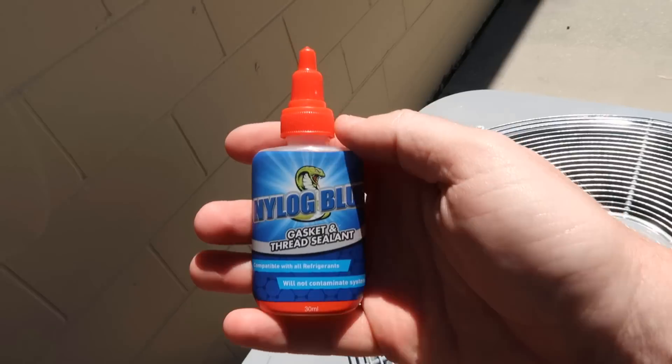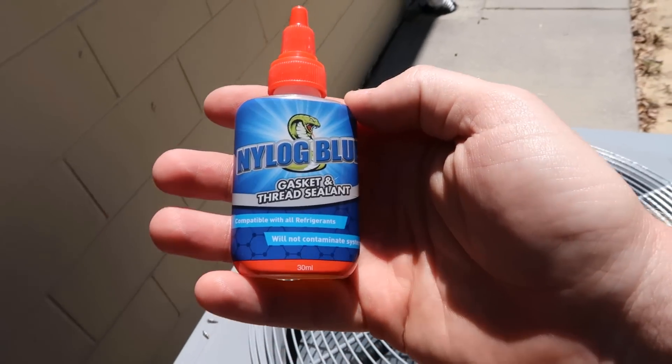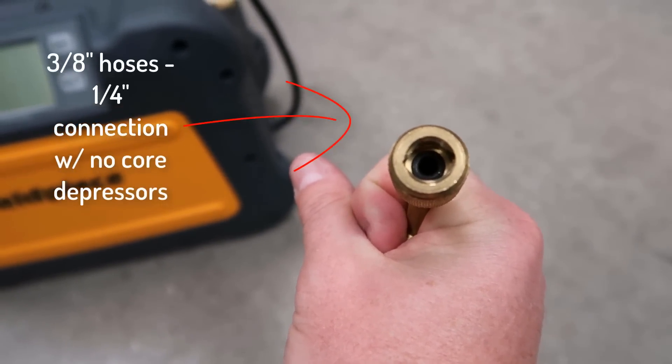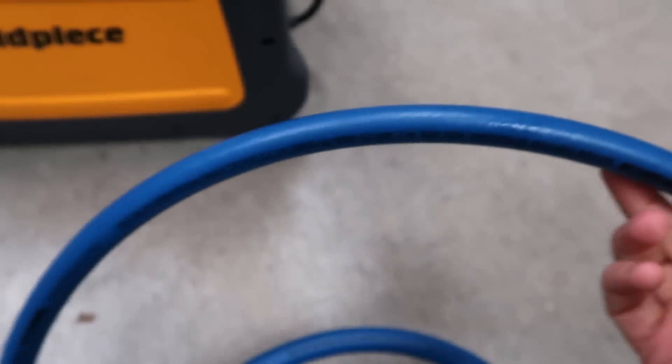We're going to use Nylog on all of our connection points for our recovery machine just to make sure that everything's nice and snug. Nylog is a great assembly lubricant — it helps make sure, especially when you're pulling vacuums as you often are when doing recovery, that you have a nice tight fit on all of your joints. I put a little Nylog on the mating surfaces of every single hose and every connection point. If you look inside these hoses, there's no core depressors in them, and they're also quarter-inch adapters but actually three-eighths hoses, so they have a lot of nice open area in them.